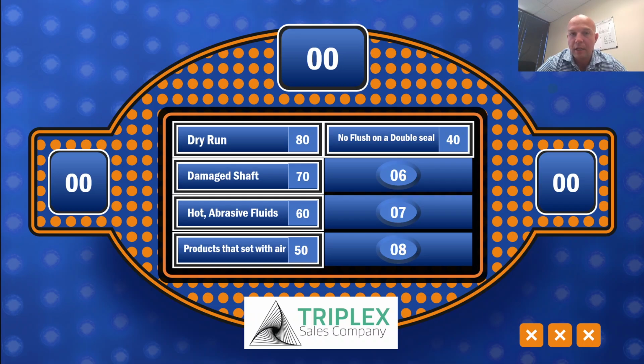And the first thing that I said was, "Where's your flush line?" Because they didn't have the flush on that outer seal. When that happens, things get really hot, and a carbon seal will actually smoke. This customer couldn't differentiate between the motor and the pump, but it was pretty clear once we saw it. So if you're running a double seal, you have to make sure you have a flush.